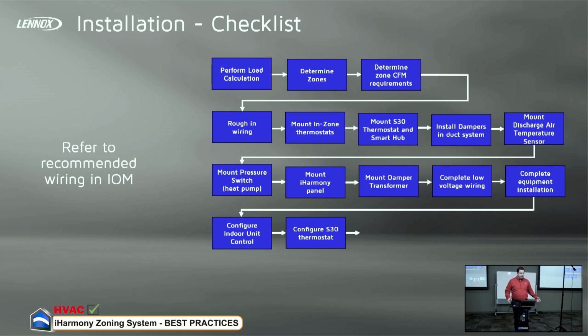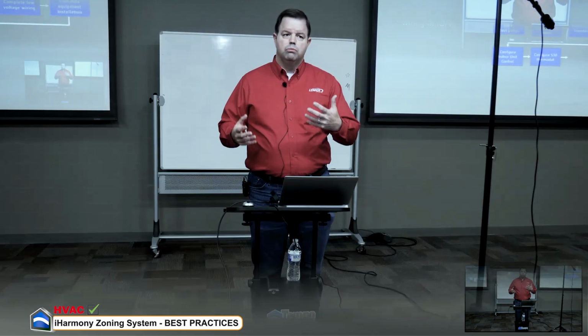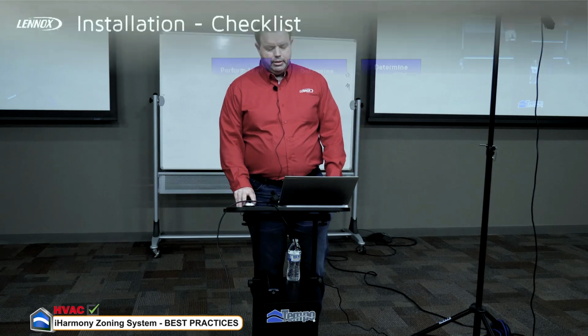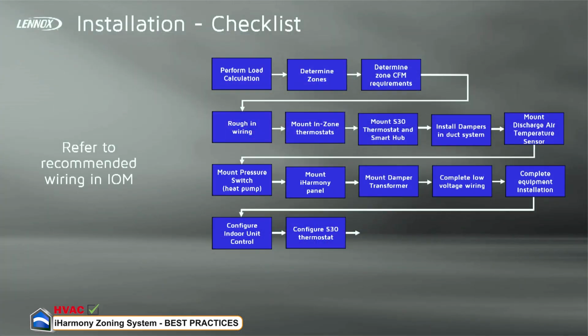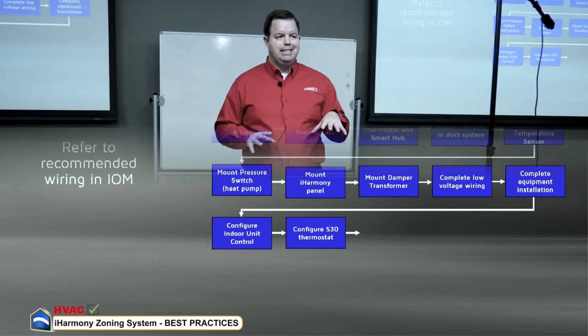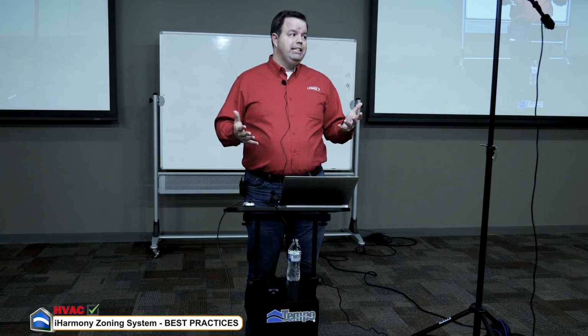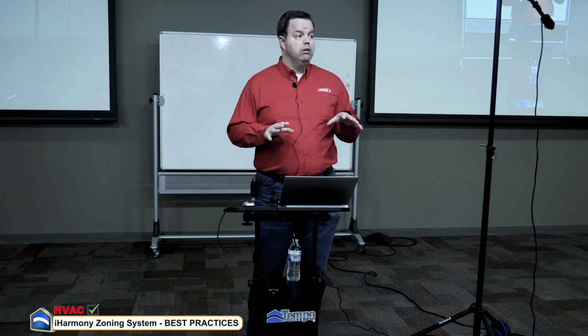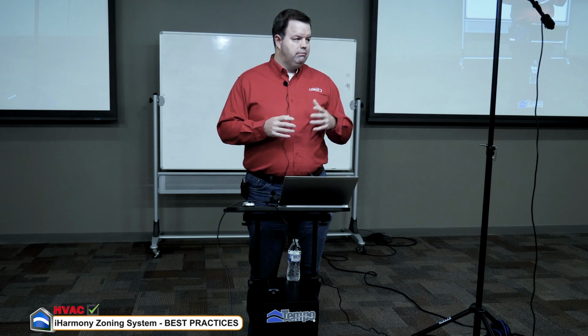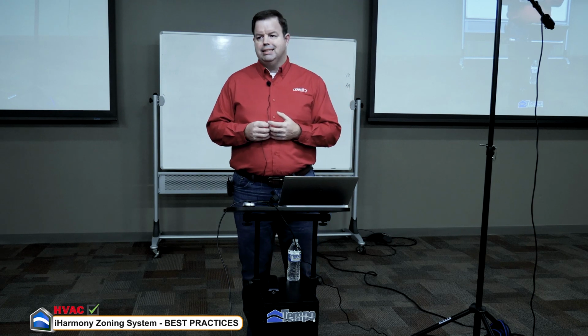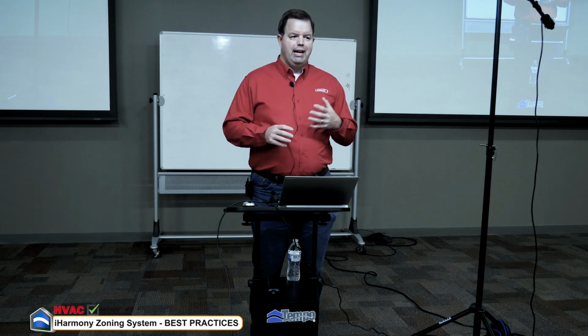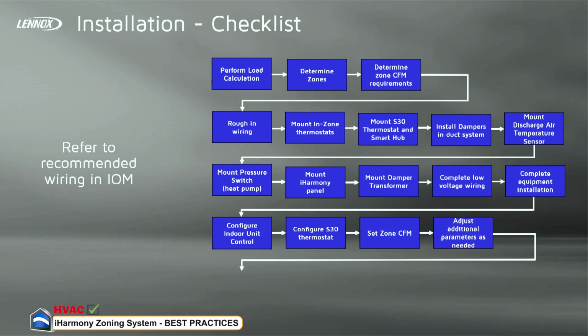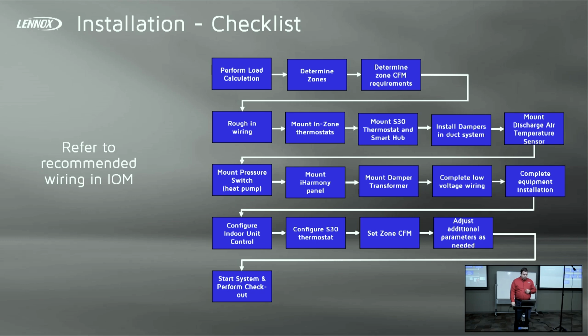So basically, once you get everything powered up, you can go through configuration. We'll look at some simple steps there, just the basics of setting up the thermostat. One thing I always tell folks about these systems is there's a lot that you can change, but there's not a lot that you have to change. The main thing that we'll look at here is making sure that your airflow is correct. That's usually the most critical point and what causes the most problems with these systems. But outside of that, there's usually not a whole lot that we have to go through to make adjustments on it.